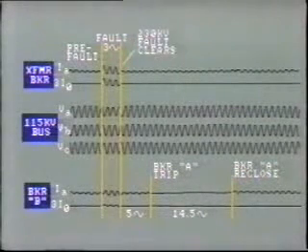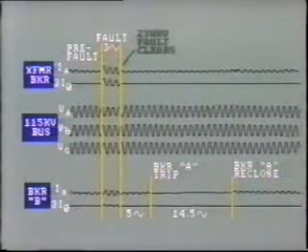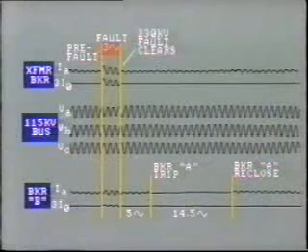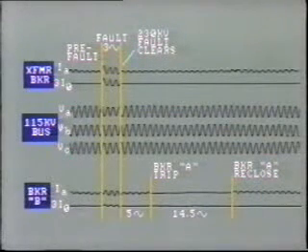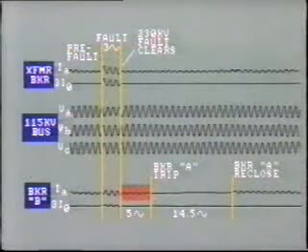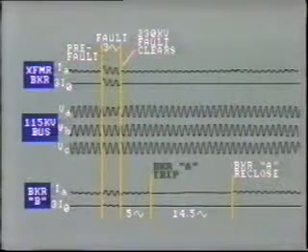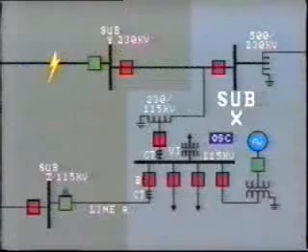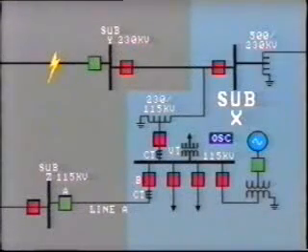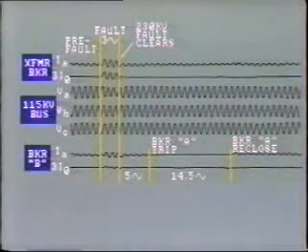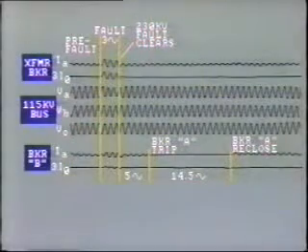Tripping on the 230 kV system was correct, and the fault was cleared in just over 3 cycles. But look at the phase current through breaker B. Normal load current flows after the 230 kV fault clears, but 5 cycles later, breaker A trips at the remote end of the line. The incoming feed from substation Z is now interrupted. After 14 cycles, breaker A recloses and remains closed.